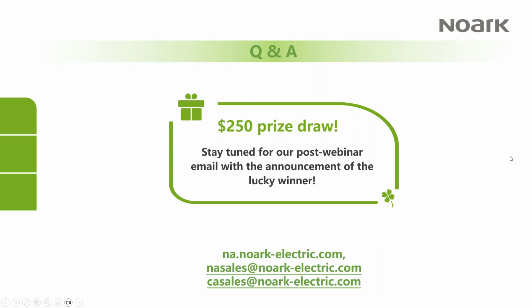After the service entrance slides and their application questions, which includes service entrance label and full-size neutrals, you've already answered the NEMA 4X. I think we answered a lot of these questions throughout, Rob. One question: I thought a service entrance rated disconnect was required to have exposed knife blade type connections. Is this not the case? No, this is not the case. The disconnecting means can be any suitably approved disconnect under the UL or CSA standards.